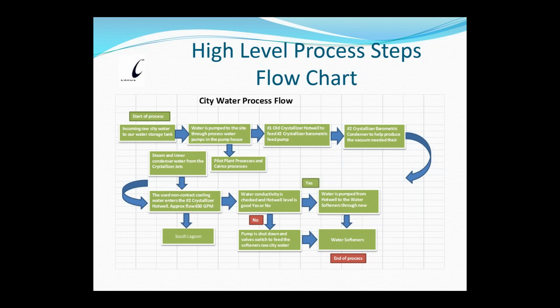How many times can you recycle the water? As far as I'm concerned, you can recycle it as often as you really want to. I mean, some of our cooling towers in the plant are a constant circulation loop, and the only time any new water is added to it is when we have evaporation to the point where the water level gets too low. With the RO system, it allows us to use water 40 to 50 times.